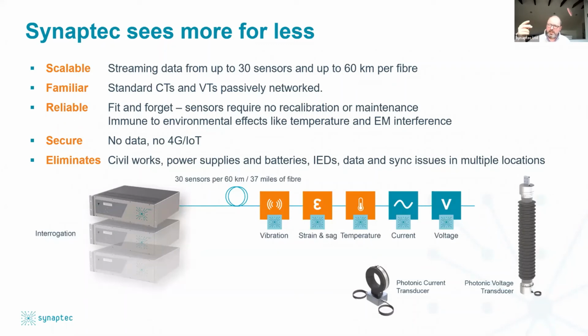The difference is that what connects them back to the central location where we have our interrogators is just a pigtail of fiber. We're passively converting an electrical value like current or voltage into strain, which changes the reflection of light in the fiber that these things reflect back. It's a single-ended system, and the fiber we're using was already available in the network, because typically, certainly here in Europe, any power network over about 66, certainly 100 kV, has optical fiber built in along the lines, typically wrapped around what we call the OPGW, or the earth wire - the optical ground wire running along the top of the circuit. There could be up to 72 cores there. Whether those cores are dark or already in use for SCADA or telecommunications traffic for the operator, we can use those fibers to reach very long distances - up to 60 kilometers per fiber, where you can get 30 of these measurements taken.